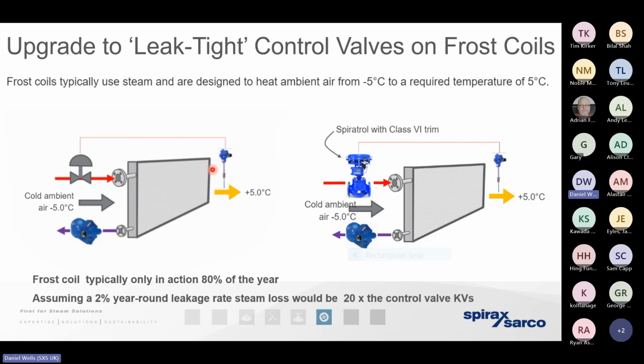So rather than have one of those traditional metal to metal class 4 control valves, as we call them, we could potentially move forward to a class 6 PEEK seat control valve. It's a high temperature polymer, and that actually gives us an excellent shutoff rate. In fact, it's impossible to measure the benefit in shutoff rate in terms of percentage. It's literally down to a few bubbles of air that would be leaking across a control valve under laboratory conditions. So we're moving towards a position where we could potentially consider that control valve as an isolation valve as well, meaning we're less likely to experience erosion, and meaning we're protecting that frost coil from any unnecessary energy loss, but most importantly from any damage.